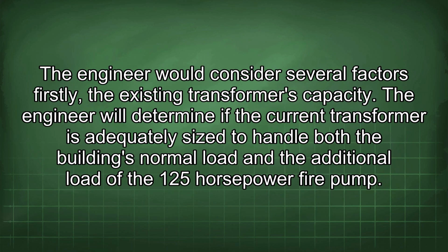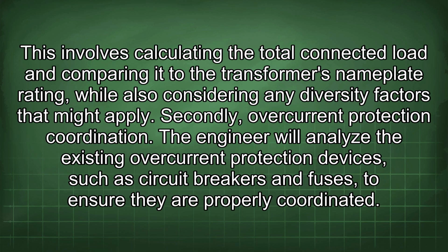The engineer would consider several factors. Firstly, the existing transformer's capacity. The engineer will determine if the current transformer is adequately sized to handle both the building's normal load and the additional load of the 125 horsepower fire pump. This involves calculating the total connected load and comparing it to the transformer's nameplate rating, while also considering any diversity factors that might apply.